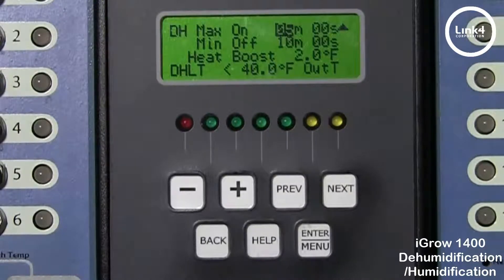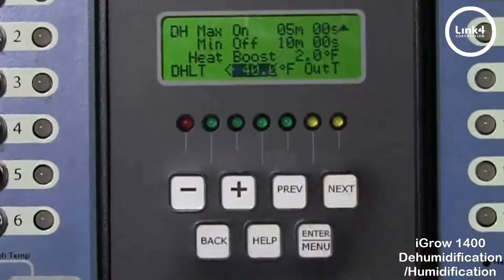Heat boost is another means of reducing humidity. With heat boost, you must have an outdoor temp sensor in order to utilize this feature. You can automatically increase the setpoint by the amount entered. The adjustment is subject to the on/off cycling. If you want to turn off the dehumid cycling, just set the min to 0. For DHLT, this value is set when the outside temperature is less than 40 degrees Fahrenheit — the exhaust fan will be turned off, the vent will go to a minimum of 15%, and the heater will help in the dehumidification process.